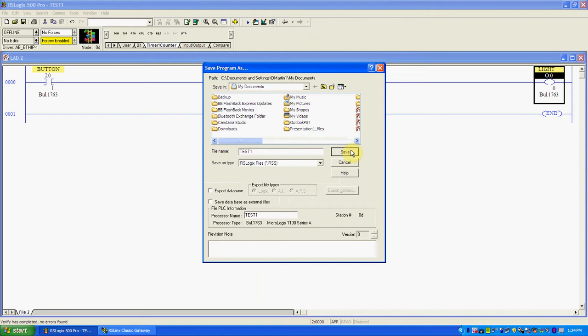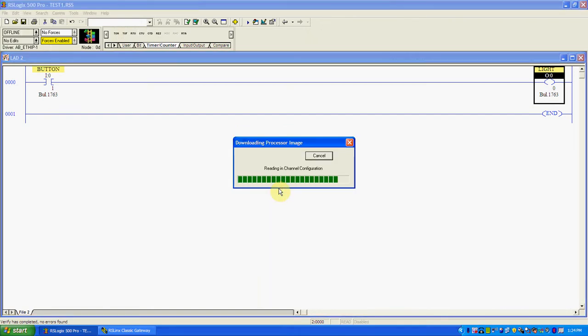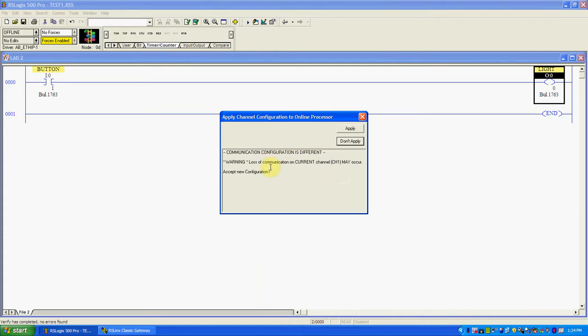I would give it a name, whatever the name was, and I could change it here. This is an important message — what this is saying is the communications path or channel is set up differently between the offline program and the online program, and they're asking if I want to apply this change, which means I'll be changing the way the PLC communicates online. Or don't apply — leave it the way it is. Obviously I'm talking to it now, so I like the way it's working. I'm going to not apply this, and I'd recommend, unless you intend to change it, choose 'don't apply' here.